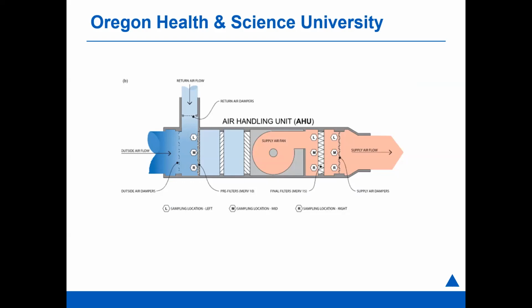The system also has higher levels of filtration—a MERV 10 pre-filter, when often it's only MERV 7 or 8, and a final filter at MERV 15, higher than the MERV 14 minimum. They sampled before the pre-filter, before the final filter, and downstream of the final filter at the supply dampers.